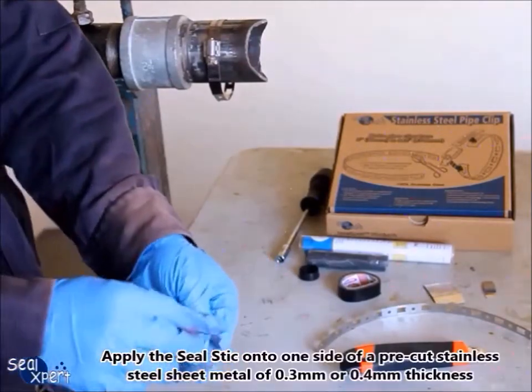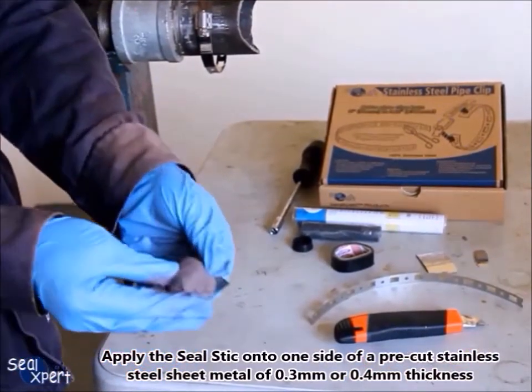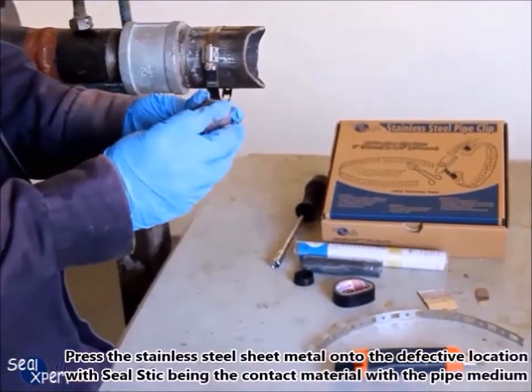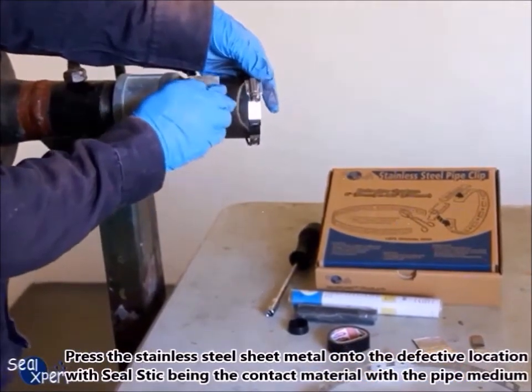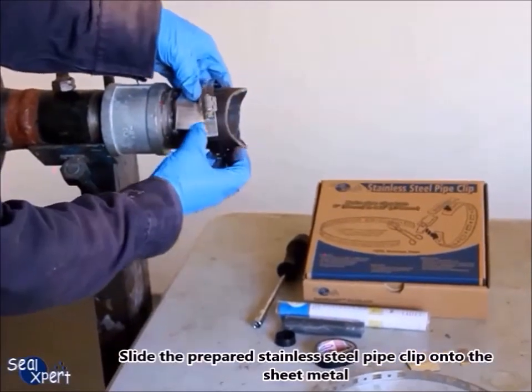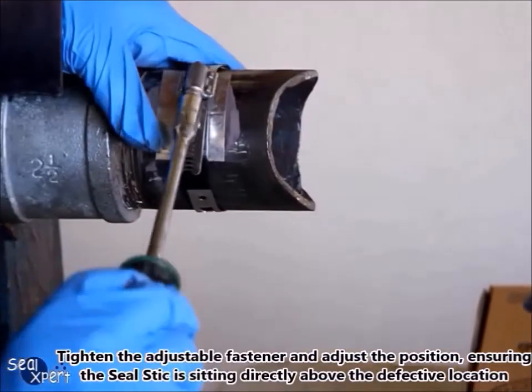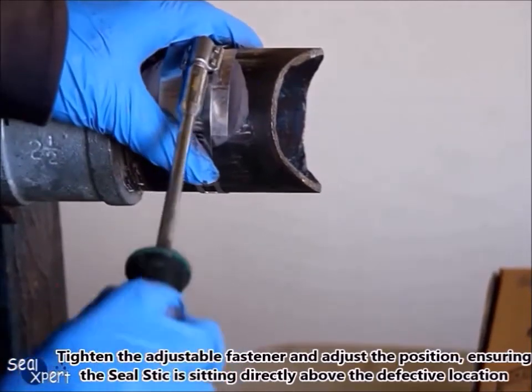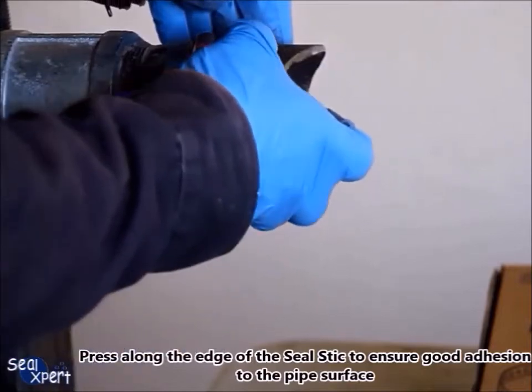Apply the Seal Stic onto one side of a pre-cut stainless steel sheet metal of 0.3 or 0.4 millimeters thickness. Press the stainless steel sheet metal onto the defective location with the Seal Stic being the contact material with the pipe. Slide the prepared stainless steel pipe clip onto the sheet metal, tighten the adjustable fastener, and adjust the position ensuring the Seal Stic is sitting directly above the defective location. Press along the edge of the Seal Stic to ensure good adhesion to the pipe surface.